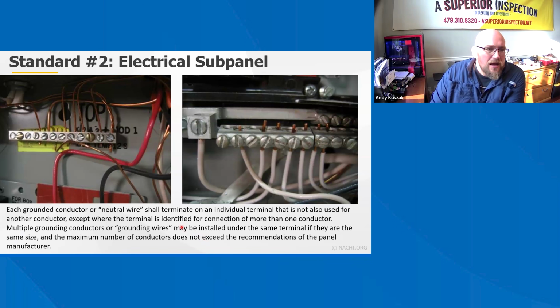So again, back to older homes that really didn't have a code implementation in your area, you're going to find a lot of neutrals, many times 3, sometimes 4, if you have a really dedicated electrician, multi-tapped on the neutral bus bar there. In my reports, this is just what I do. I'm not recommending that you do this. I'm just telling you from my perspective. I put in my reports that multiple conductors underneath a single lug is not recommended due to continuity issues.